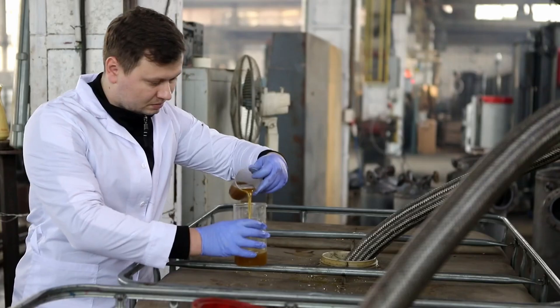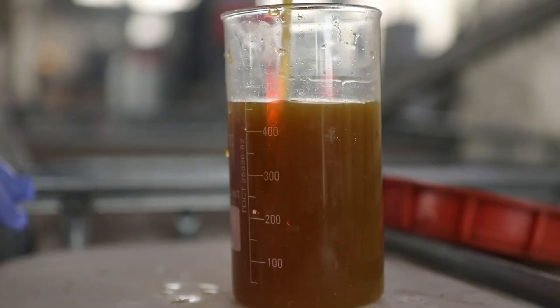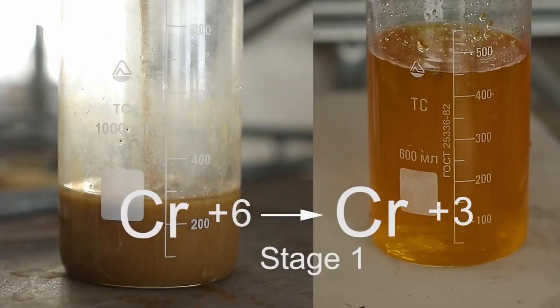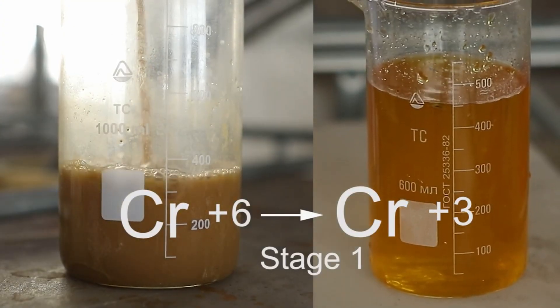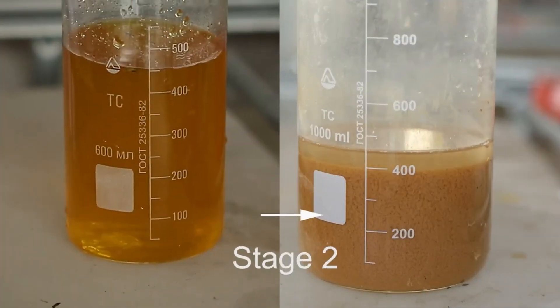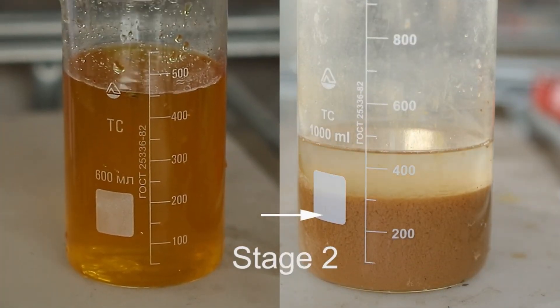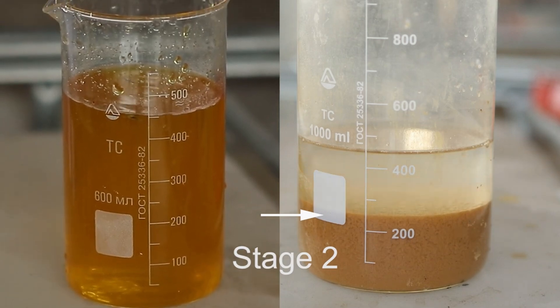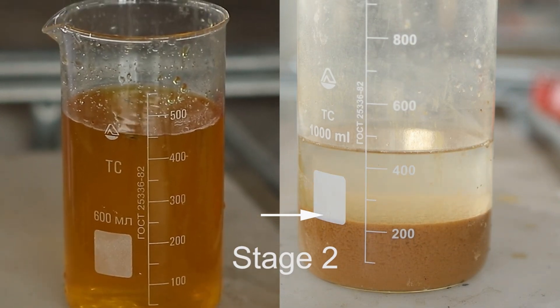If hexavalent chromium concentrations are high, a two-stage treatment is recommended. At the first stage, more toxic hexavalent chromium is converted into less toxic trivalent chromium, and at the second stage, trivalent chromium is converted into poorly soluble compounds after interacting with a chemical agent and removed as a precipitate.